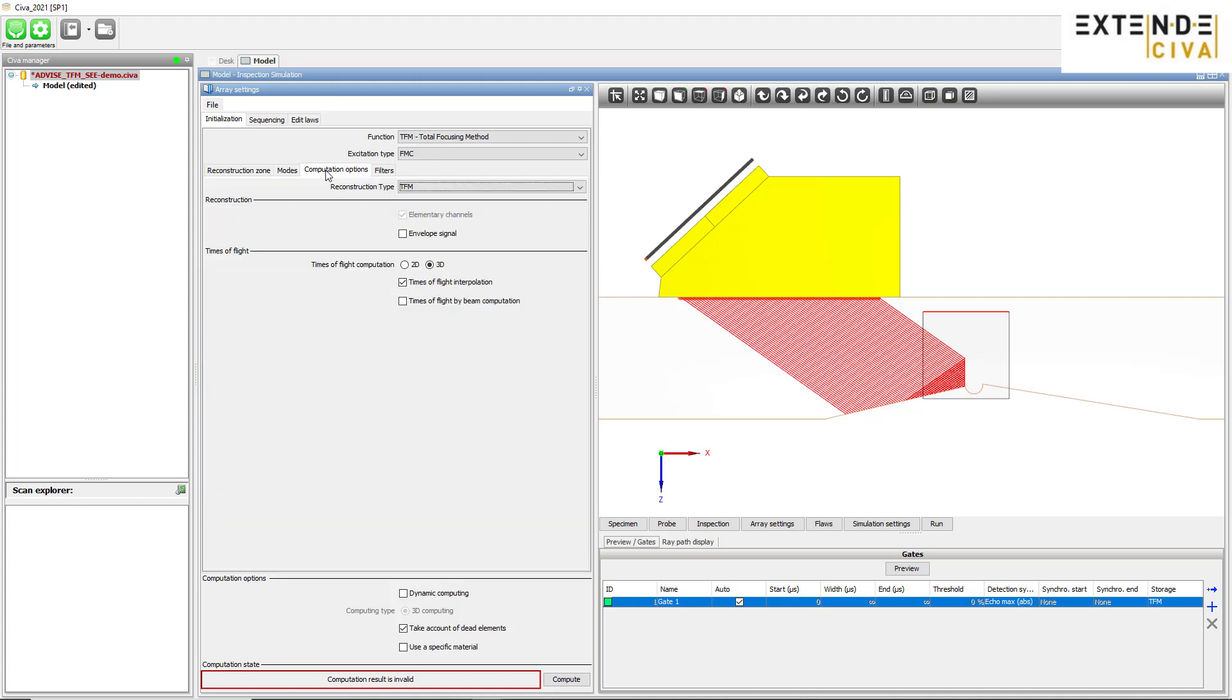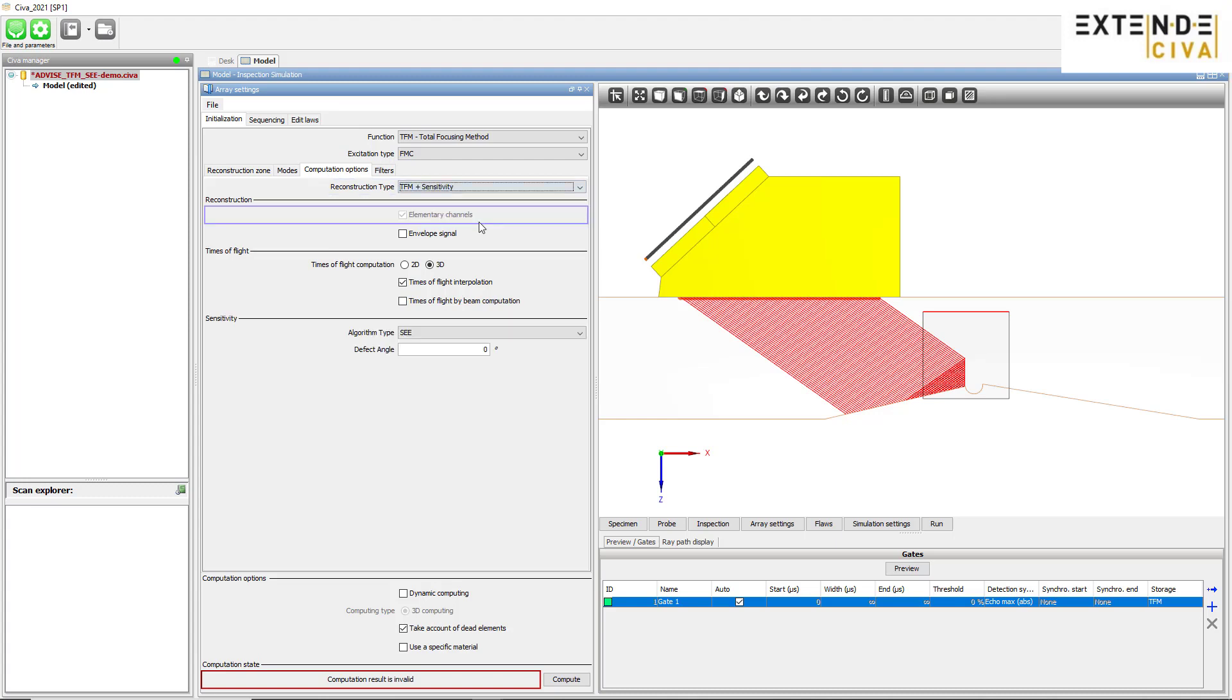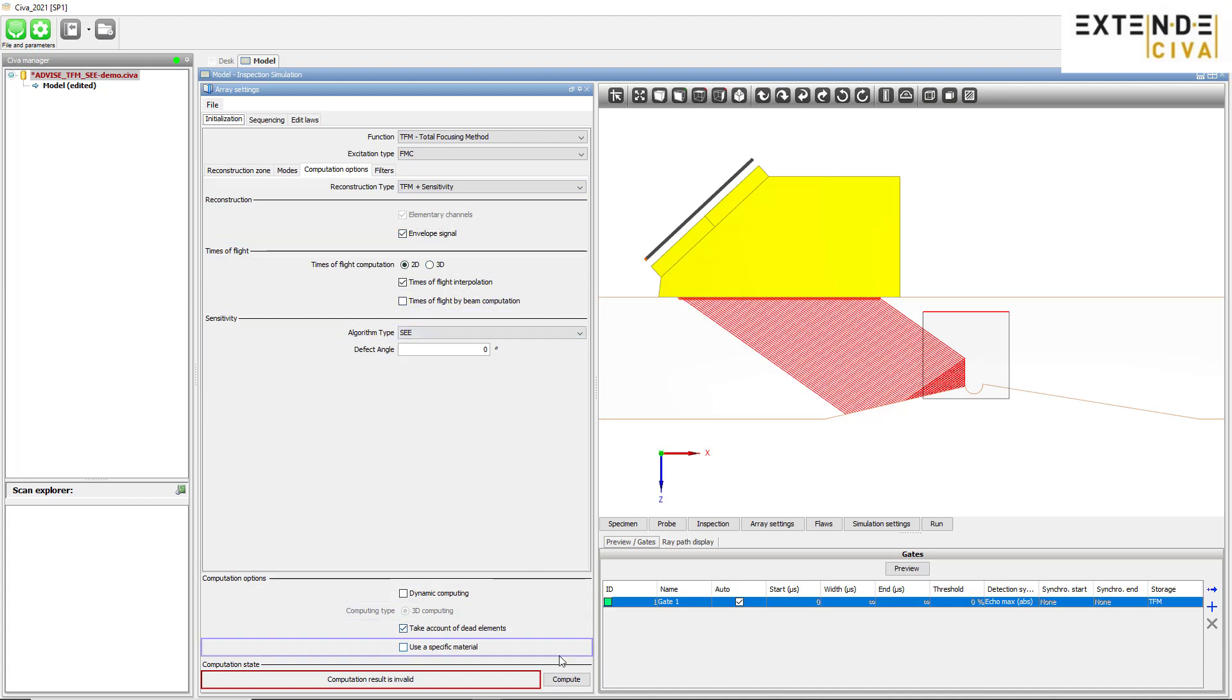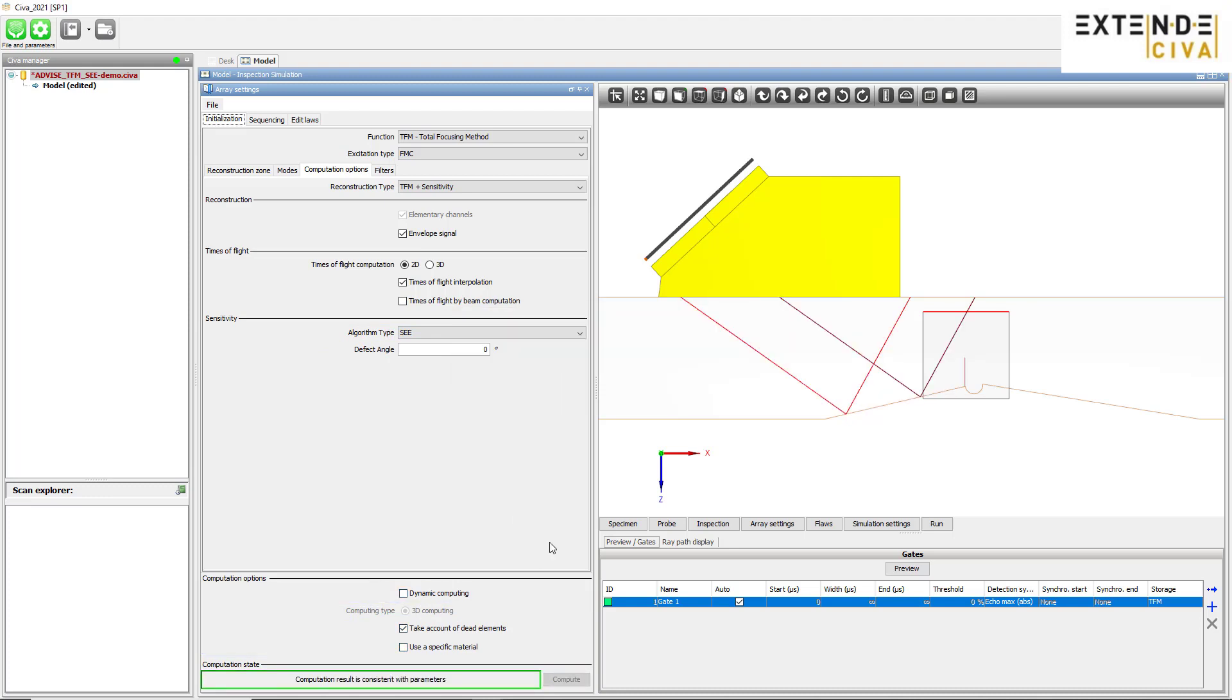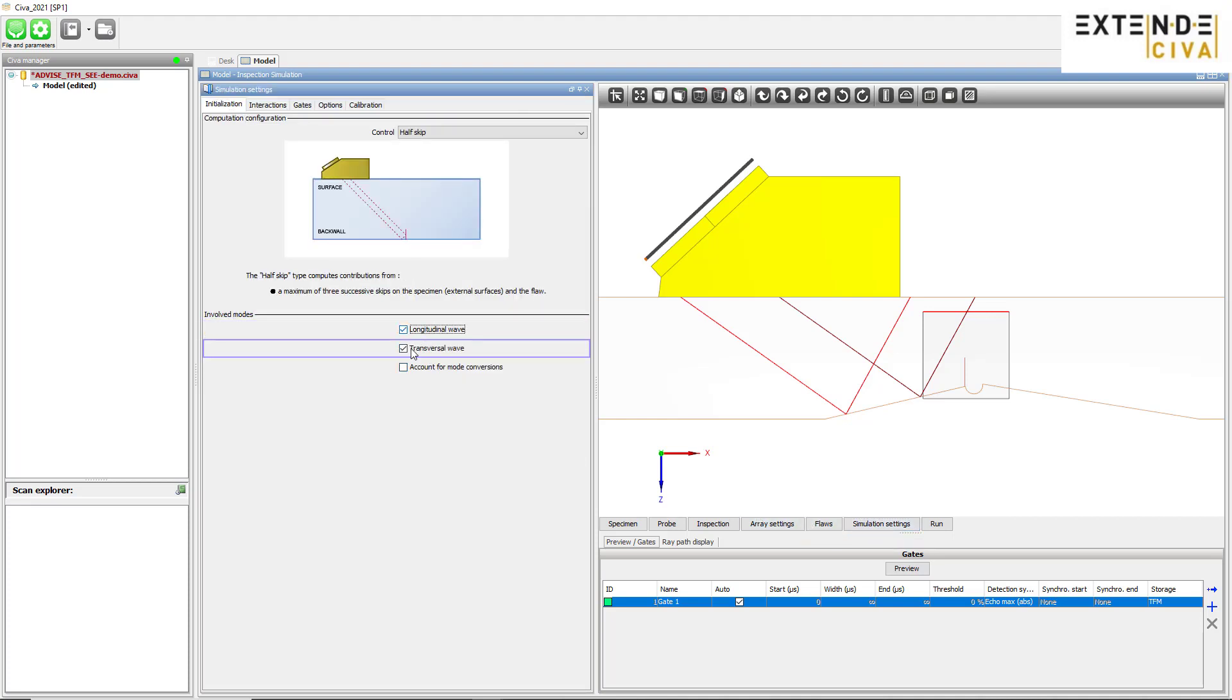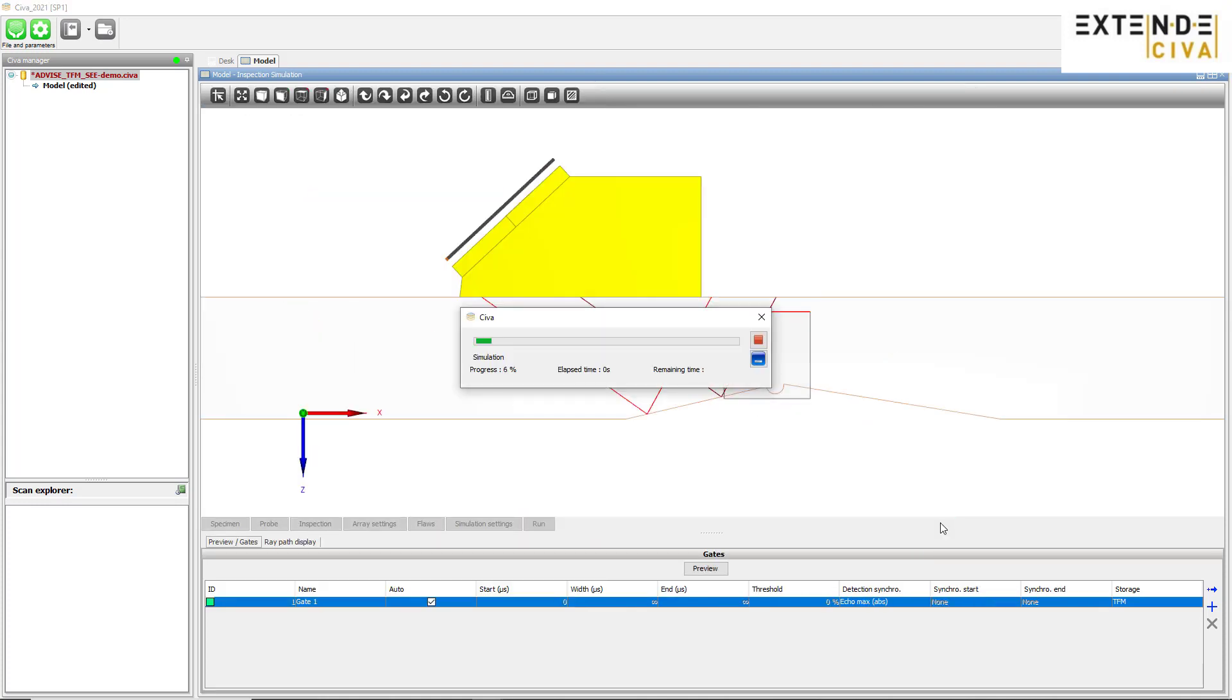In the Computation Options tab, we choose TFM plus Sensitivity to get both TFM images and C mappings. Then, we compute the times of flight. In the Simulation Settings panel, we finalize the configuration by selecting Half Skip mode and enabling L, T and Conversion modes. We then run the computation.